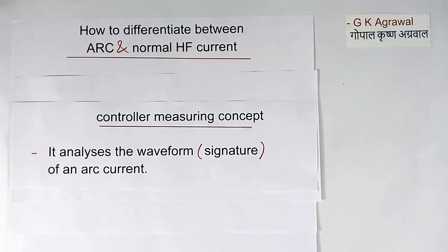Now after measuring so many parameters of the current waveform, controller will analyze the waveform of the arc current. This is also called the signature. High frequency current is produced by many equipments, but the nature of high frequency current or nature of the high frequency waveform will be different for different equipment. That waveform is called the signature. By seeing that waveform, controller can tell it is due to arc current or due to some other reason.